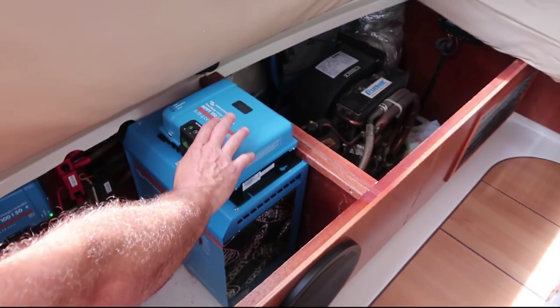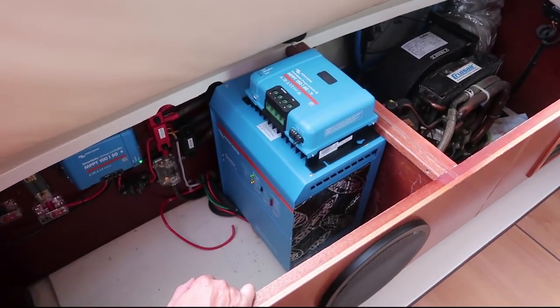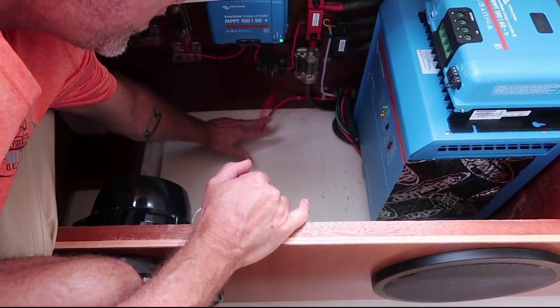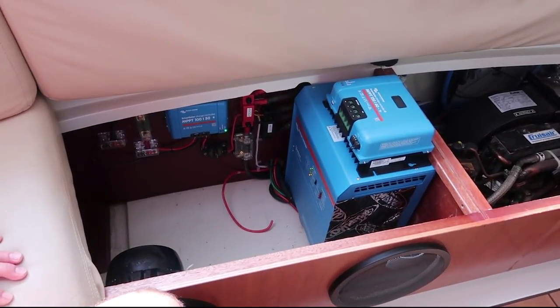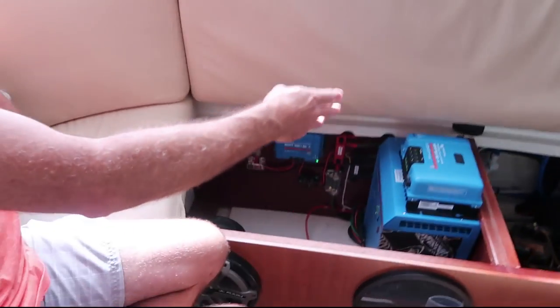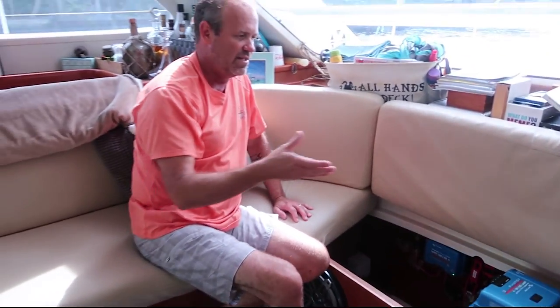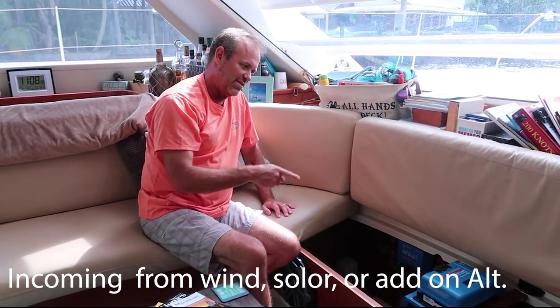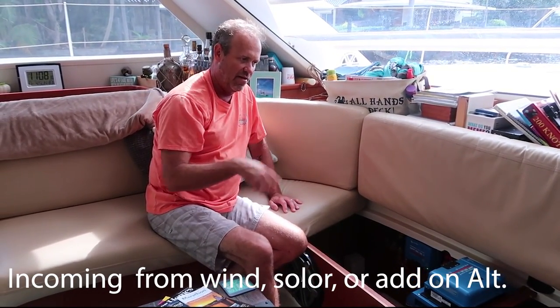Now we've got this guy up here. This is our 150-60 amp, and basically what that's going to do is we're going to mount that down here. As you can see here, I've already run the wire for the alternator, and we've got the wires over here for the solar. So this will be our solar controller. Basically it's going to take our 48 volts, or anything else that's higher voltage to charge our batteries, and that's going to feed our battery bank and help keep it charged when the generator's not running or we're not on shore power.